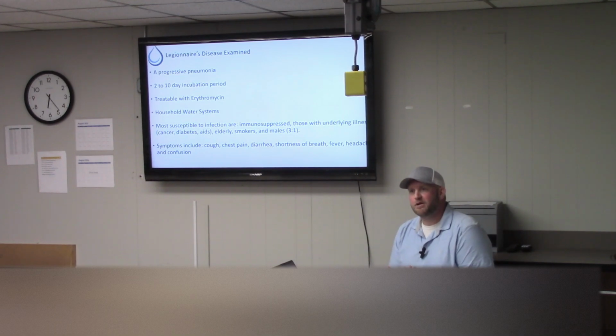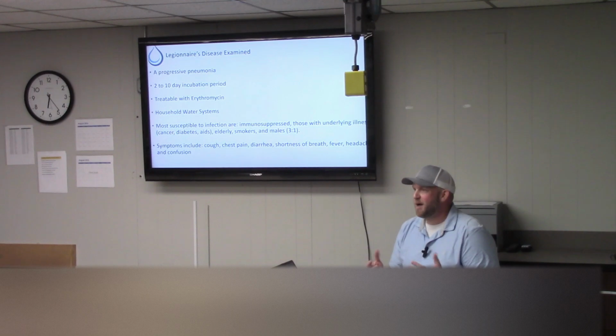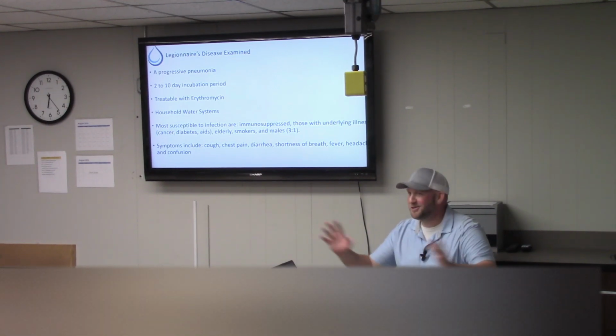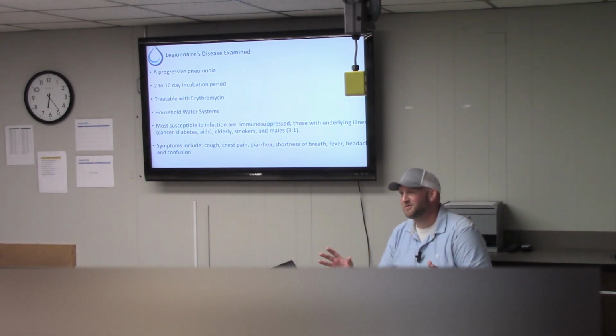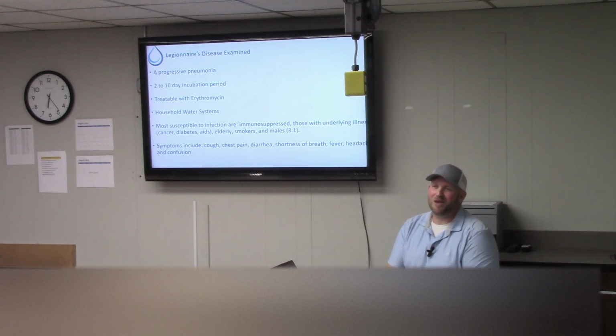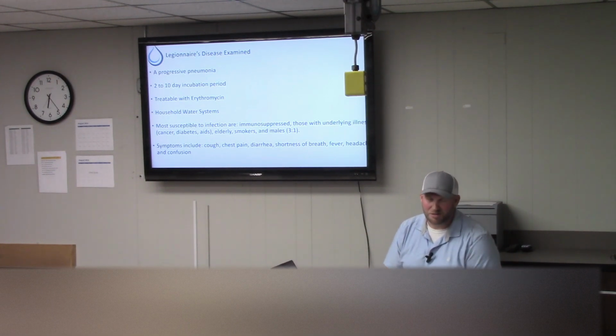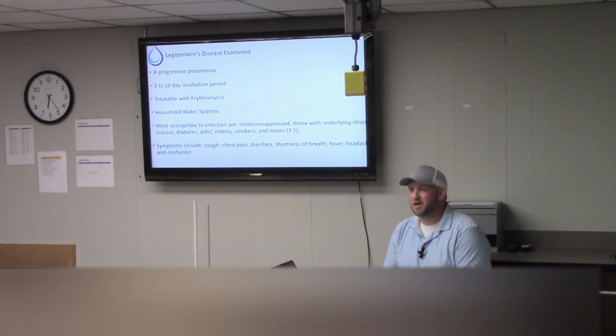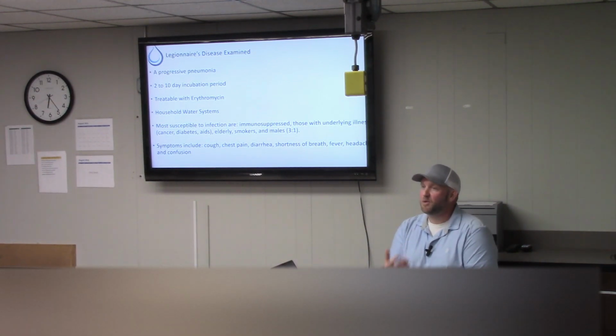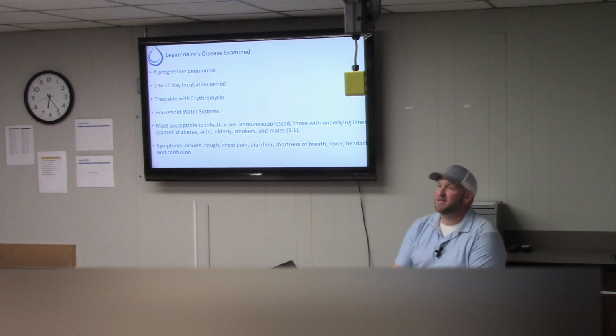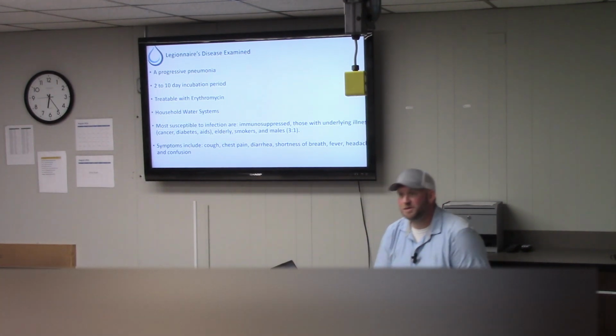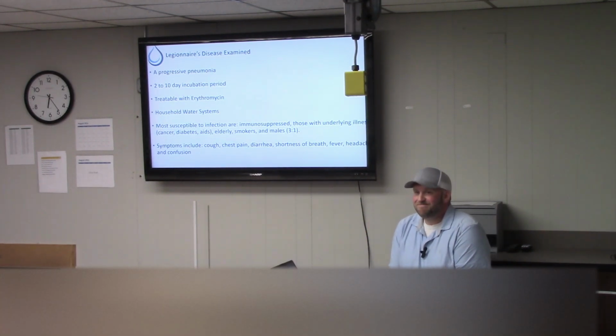Before you break into a cooling tower and perform work on it, typically what we do for our clients is go in and clean it first — we call it the nuclear bomb. We make sure there's nothing bacteria-wise that could have lived, then we drain it and do whatever maintenance needs to be done. It's the best practice way, in my opinion, to make sure the workforce completing that task doesn't end up with something happening to them that you don't want. No good deed goes unpunished as it is — let's not make it worse.